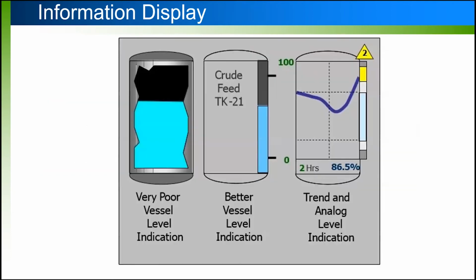Now let's look at some more traditional ways to show things versus a high performance way. This vessel here, I've got to say I've been guilty of using something similar to this dozens of times as I've built screens. This one in the middle is actually a little bit better, but the one on the right is what's recommended to use with high performance HMI, and this is what we're recommending today. So you don't just look at a tank level, you look at information about the tank level, with the last one you see where the tank level's been, whether it's rising, falling, or holding steady, and whether it's in its normal range, abnormal range, or alarm range. You can get all that very quickly with this type of display.